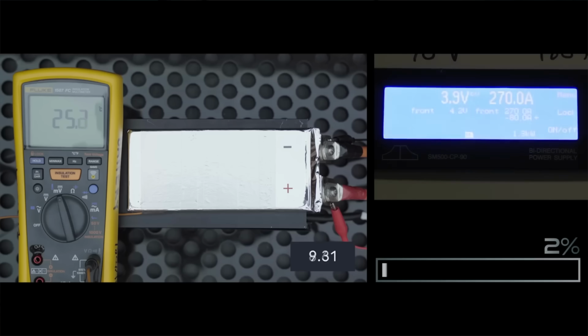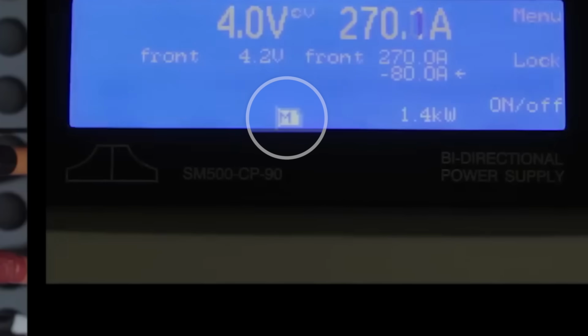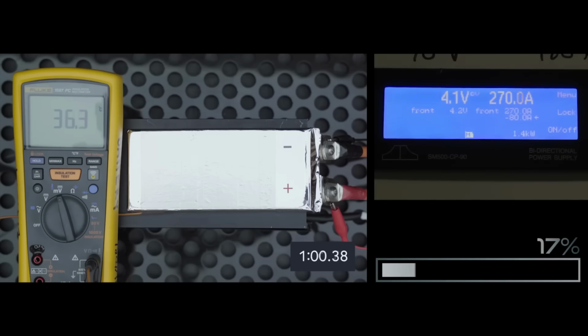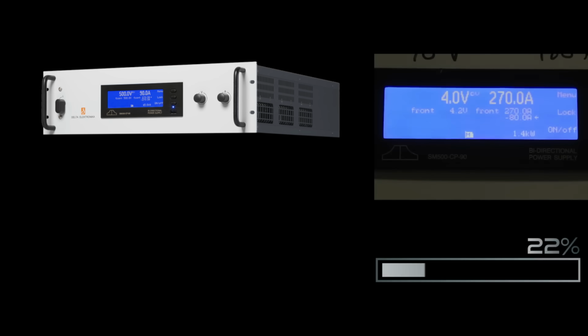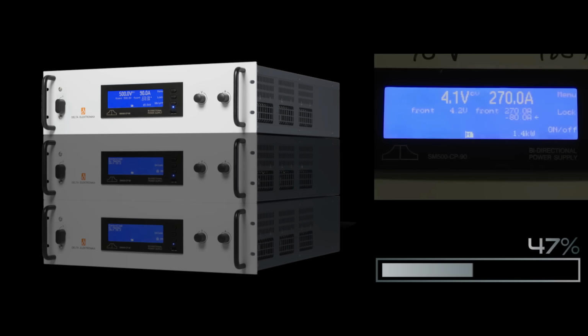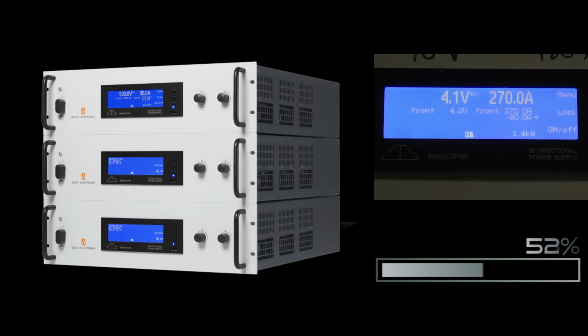Here's the next point: if you look down here, it has an M on it. The power supply they're using is the Delta Electronica SM500. It's a bidirectional power supply that can output 90 amps of current. So to get to 270 amps for that one little pouch, they actually had to use 3 of these, and that M designates that one as the master.